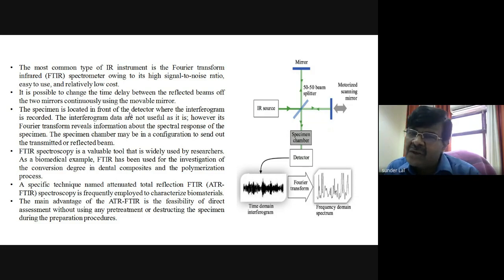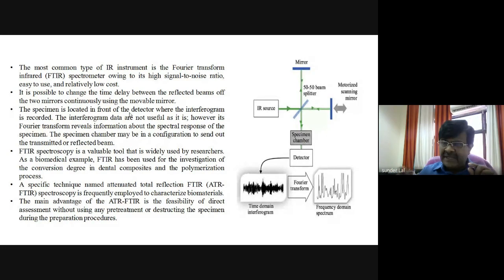The FTIR spectrometer, owing to its high signal to noise ratio, is easy to use, as I said, and relatively low cost. And it is possible to change the time delay between the reflected beams of the two mirrors, which is shown in this figure. You can see it is possible to change the time delay between the reflected beams of the two mirrors continuously using the movable mirror. Next, the specimen is located in front of the detector, where the interferogram is recorded.